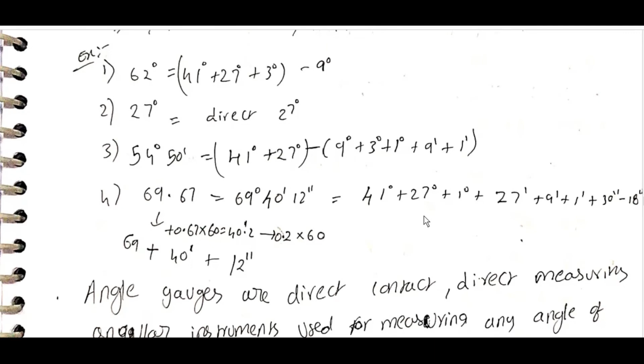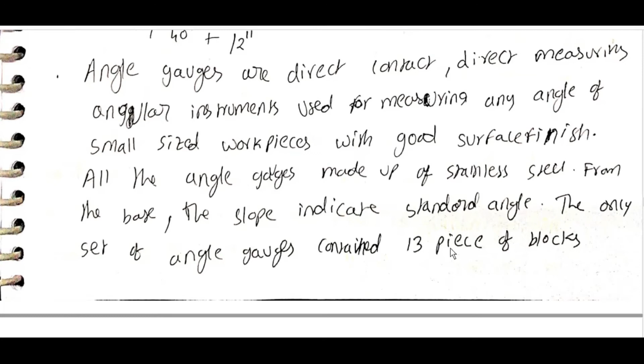Angle gauges are direct contact, direct measurement angular instruments used for measuring any angle of a small-sized workpiece with good surface finish. All angle gauges are made of stainless steel. The slope from the base indicates the standard angle. One set of angle gauges contains 13 pieces of blocks, and an extra 90 degrees block is supplied to measure larger angles.